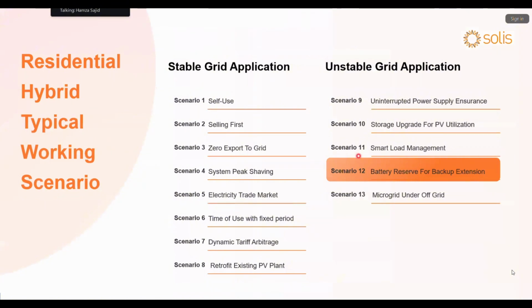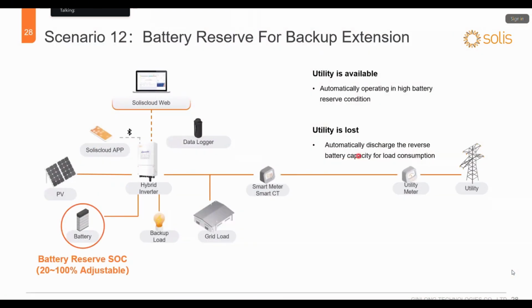Okay, battery reserve and the battery backup for backup extension. Now you can set a battery reserve SOC, like whatever you are utilizing or generating from the PV, you can set the battery limit. Like this much power should be reserved in the battery, 50%, 100%, or 80%. So even if the PV is available and the grid is available, it will not discharge the battery and keeps that point available for any uncertain grid outage. It can still support the load. So you make sure this much power will be available even if the grid is not available.